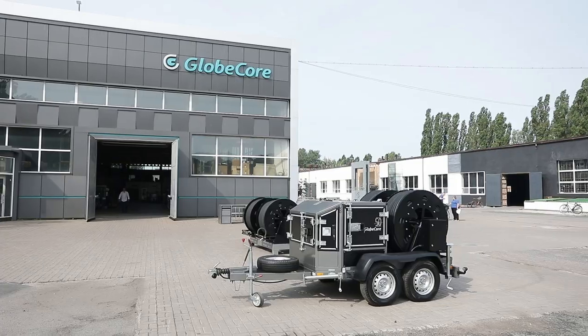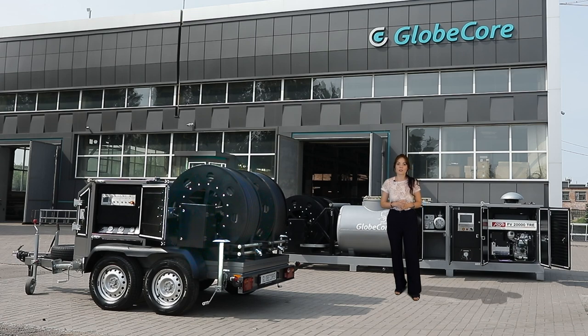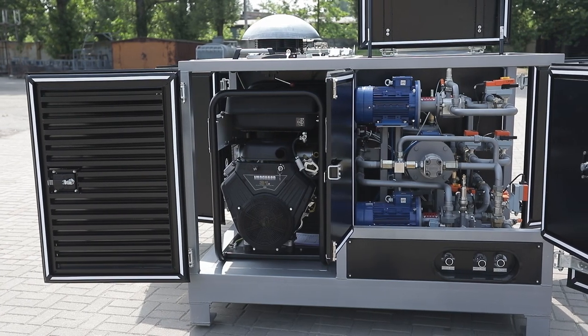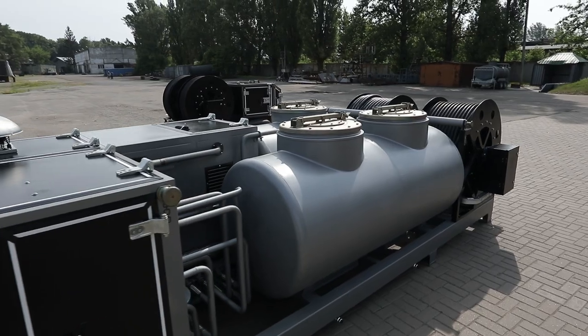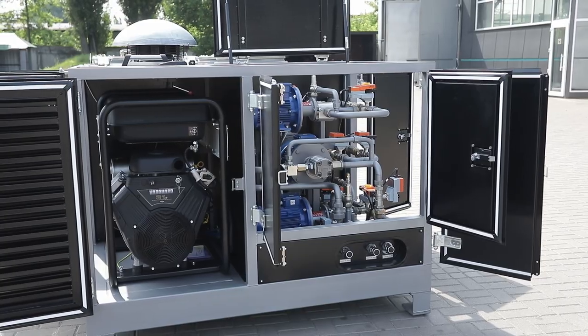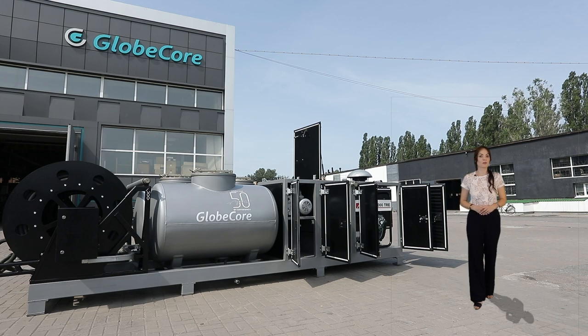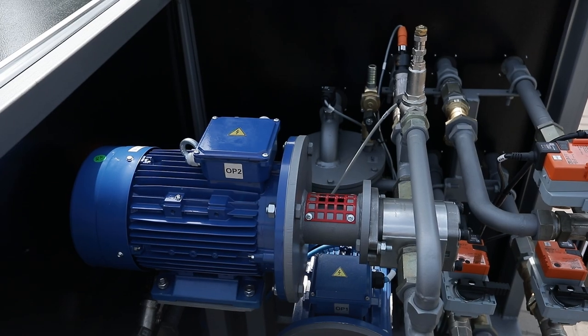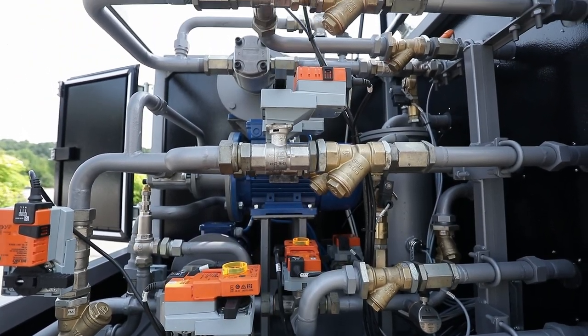If the CMMG light oil changer is well suited for servicing wind turbines on land, then the next model from this series was made for servicing wind turbines operating both on land and at sea. It is the CMMG premium oil changer. Its main differences from the previous model are the presence of two integrated tanks for clean and contaminated oil of 950 liters each, and the presence of a gasoline generator for autonomous oil changer operation in areas where there is no technical possibility of connecting to the power grids. In addition to the used oil drain mode and the clean oil supply mode, the CMMG premium oil changer also has a gearbox flush mode and heating mode. Heating the oil reduces its viscosity, allowing use of the oil changer in harsher climates, and units productivity increases.